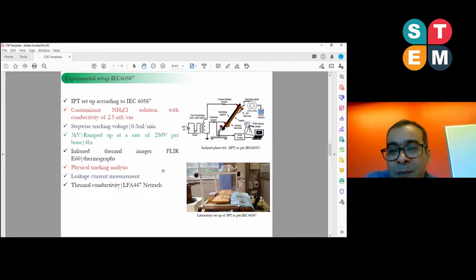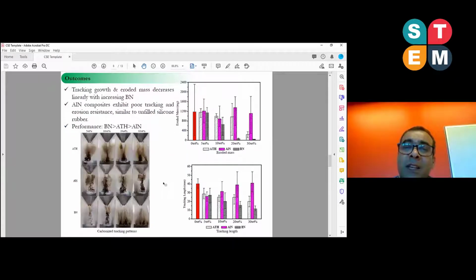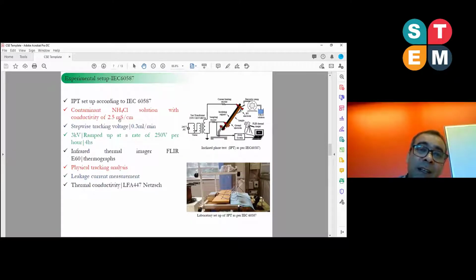Meantime, at the end of the experiment, we measure the physical tracking on the inclined plane. We measure the leakage current, and separately we measure the thermal conductivity of the insulation as well. So here are the outcomes. It is a total 4-hour experiment. In the initial hour, we start the experiment with 3 kV, and the contamination solution flow rate is 0.3 milliliter per minute. Then every hour we ramp up the voltage by 250 volts per hour. So the total experiment lasts for 4 hours.